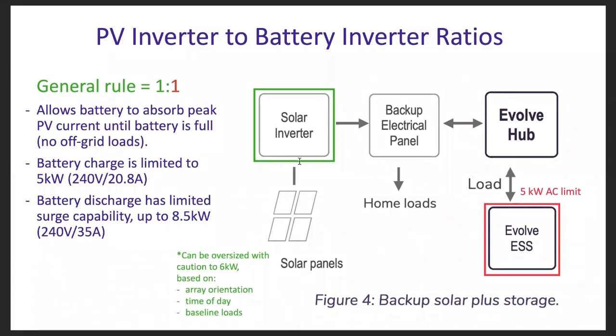As far as the sizing, that general rule of 1-to-1, that is the by the book answer. That is because the peak excess PV current needs to be below 5 kW. In applications, as this little note says here, with some caution, the AC nameplate can be oversized to a maximum of maybe approximately 6 kW, 5,800 watts, based on array orientation, time of day, and baseline loads. You can pretty safely assume that excess PV is going to be less than 5 kW at any point. So with some caution, I think a little bit of fudge factor can be taken into account here.